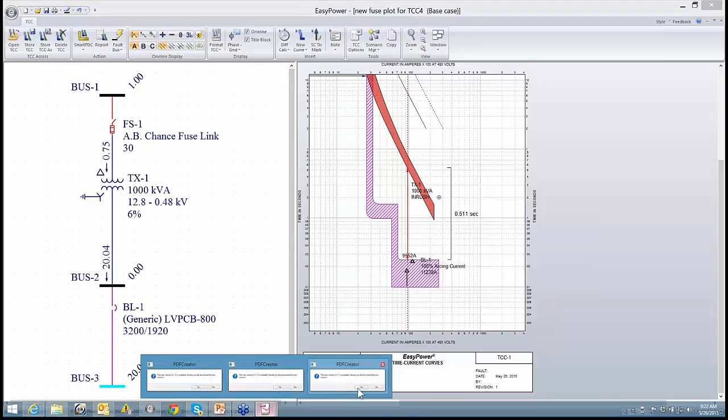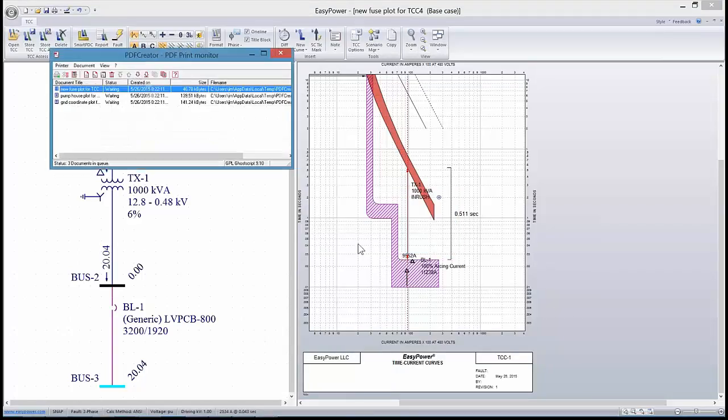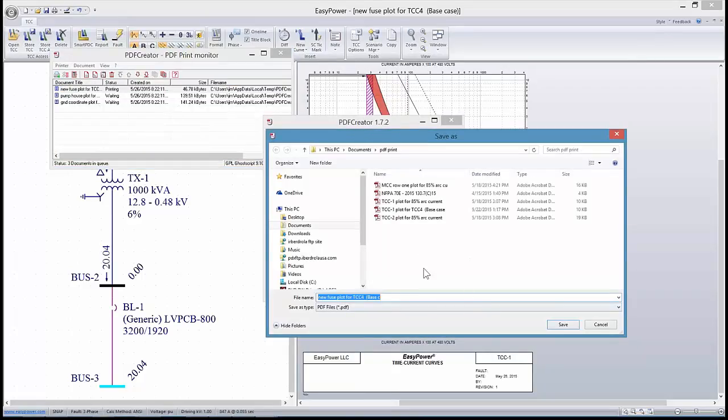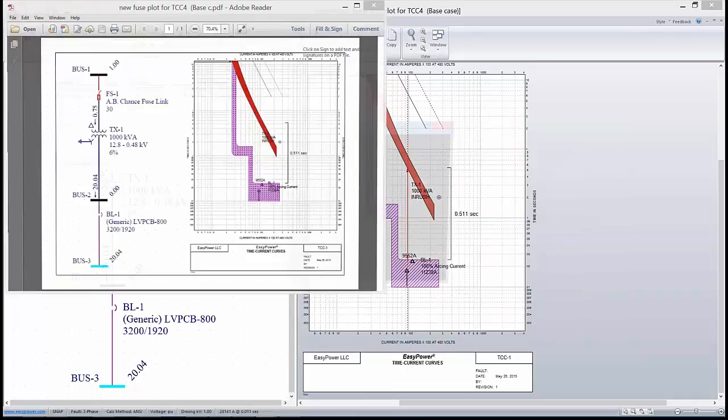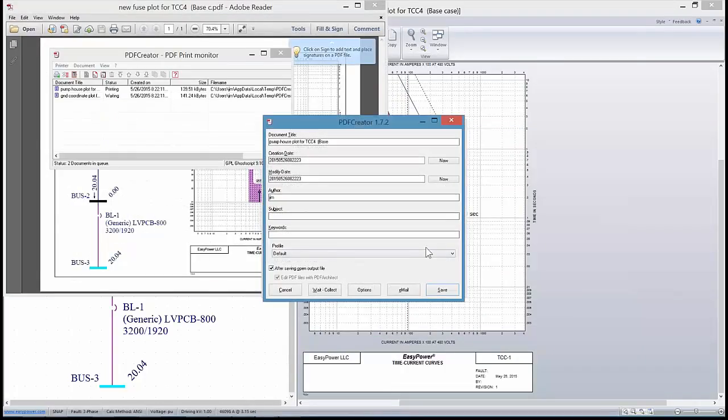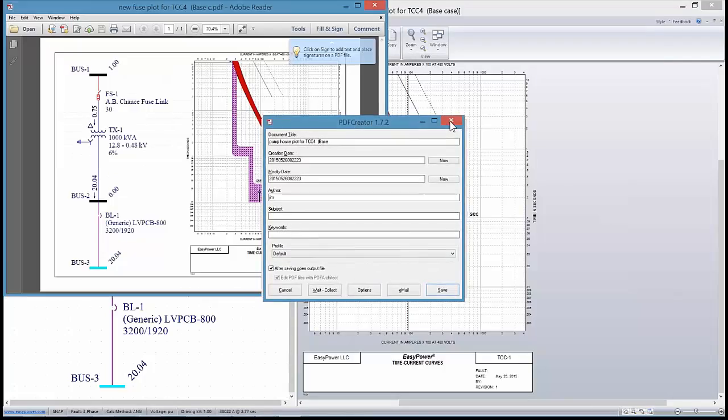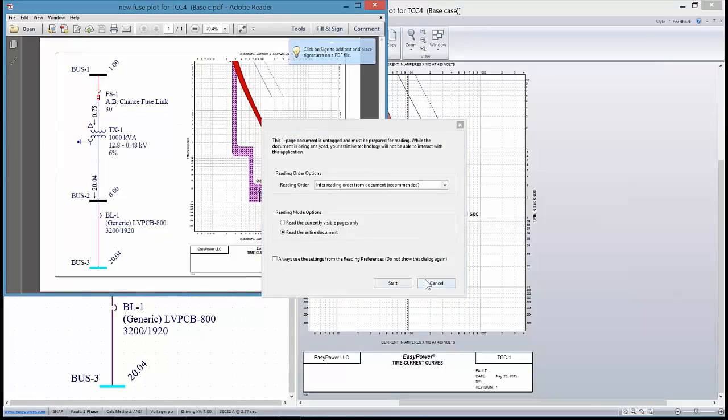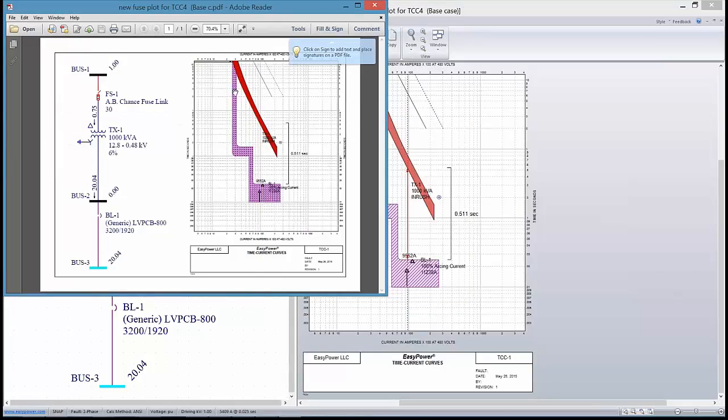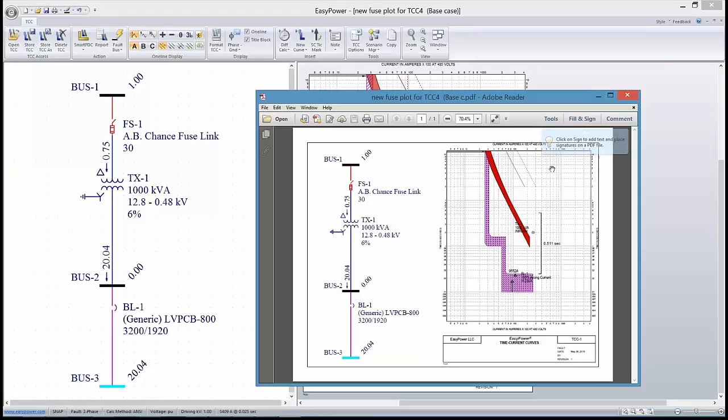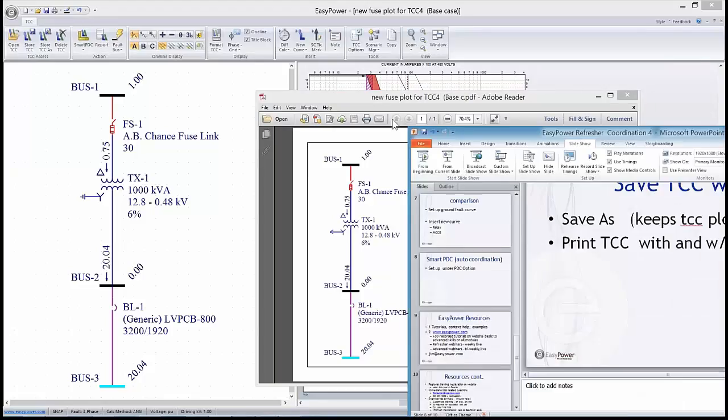Once we go to print that, let's print all three TCCs along with it. And print these in a PDF form so we can find them. So here's what the report looks like. It's giving me all three, because I asked for all three. Here's our one line diagram, our TCC curve with the annotation and the difference separation. Obviously you can modify the title block and have your own logos and whatever text you want in the file.